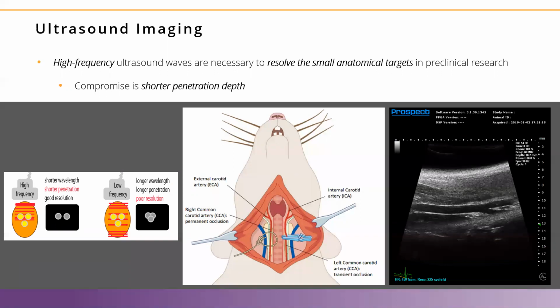The trade-off always with ultrasound is that as you increase the frequency of sound, you do increase resolution, but you decrease penetration. And so that's where we don't use the same frequencies on humans as we do on mice and rats. With the frequencies used on the Prospect T1 and other high-frequency ultrasound systems, it's really no problem to see any of the anatomical structures within both mice and rats.